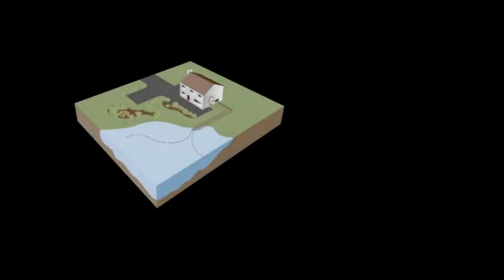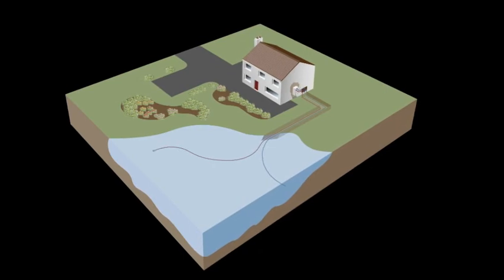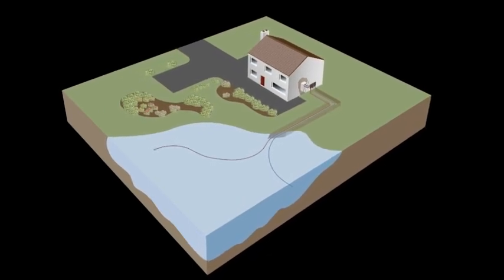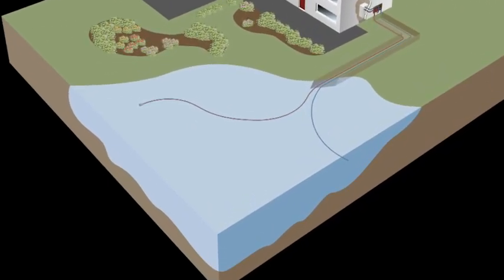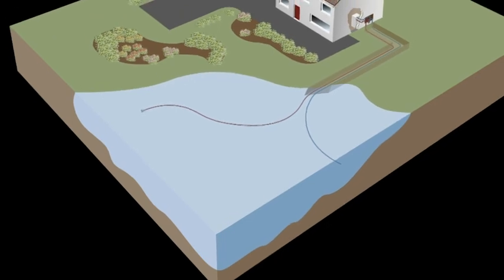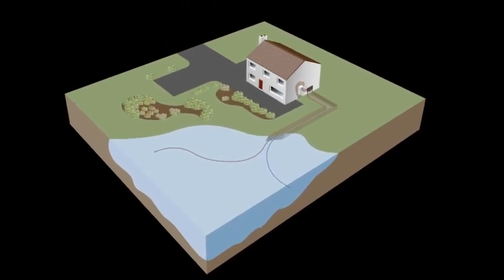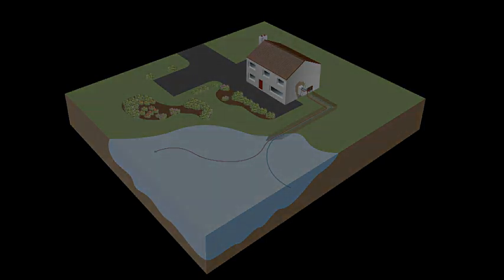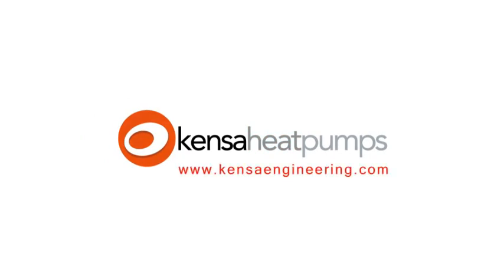In addition to closed loop ground arrays, you may consider an open loop system. Open loop systems extract energy from one water source before discharging it downstream or into a second water source, where the water itself is pumped through a second heat exchanger or an open loop rated heat pump. Open loop systems are generally used when there is a flowing river next to the property due to lower install costs. However, care has to be taken with extraction and disposal licences, and depending on the filtration system, frequent maintenance may be required. Further information on ground array designs and installations can be found in Kensa's information library at www.kensaengineering.com.